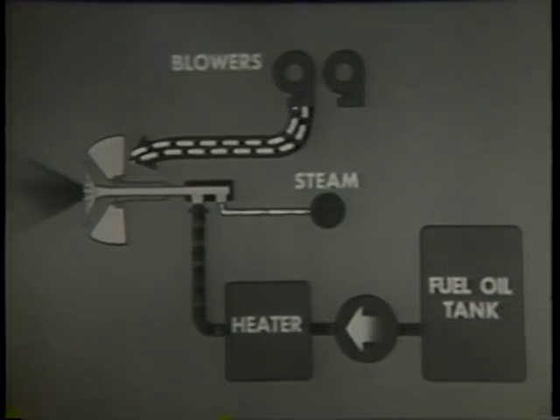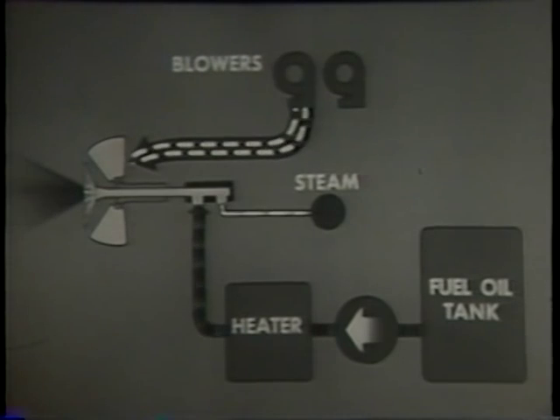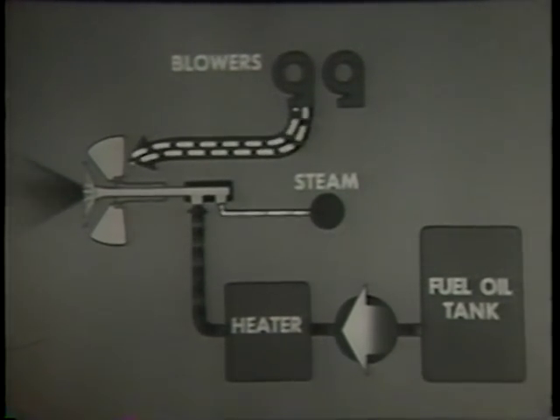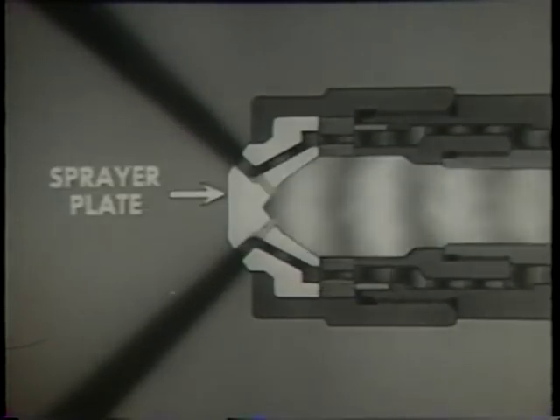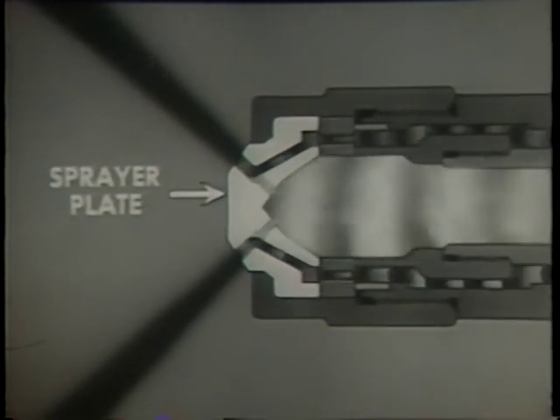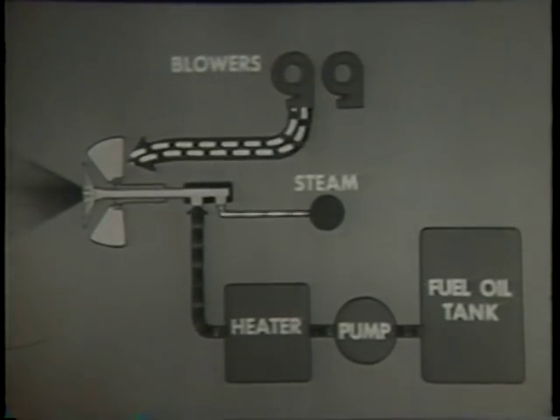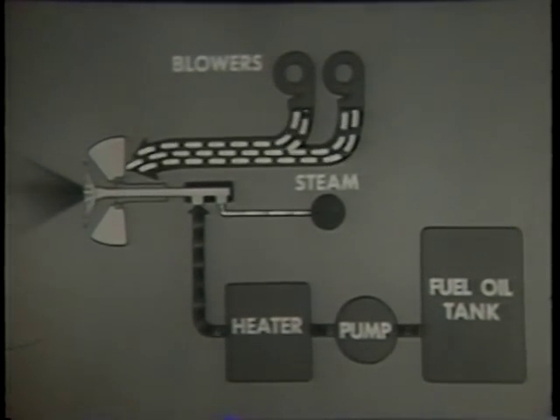Control of the steam atomizing burner involves regulating the air, oil, and steam supply. Regulate oil pressure to control the quantity of oil. When you increase or decrease oil pressure, you must change the steam pressure correspondingly to get good atomization. You must also change the sprayer plate in the burner if the capacity of the plate is incorrect for the new firing rate. As with most burners, you adjust the speed of the blowers and the number in service to control the air supply.